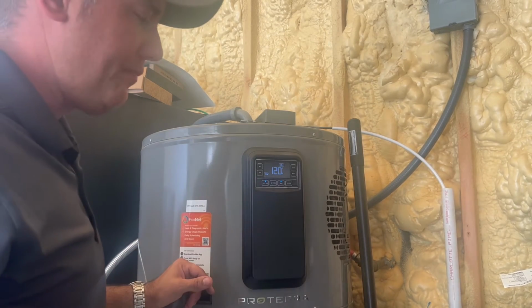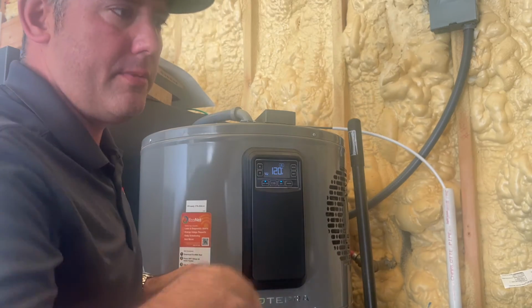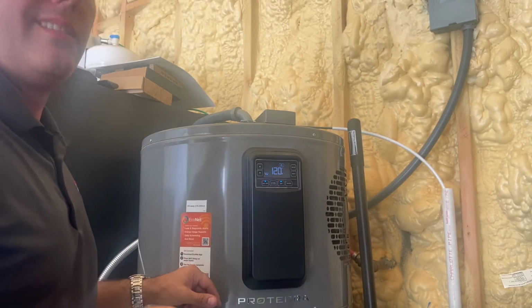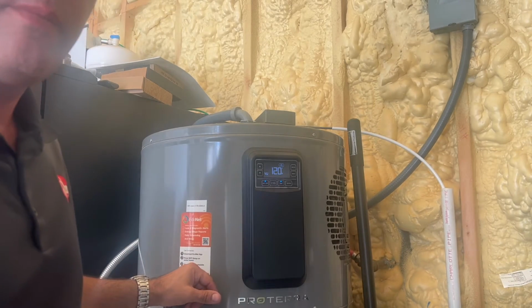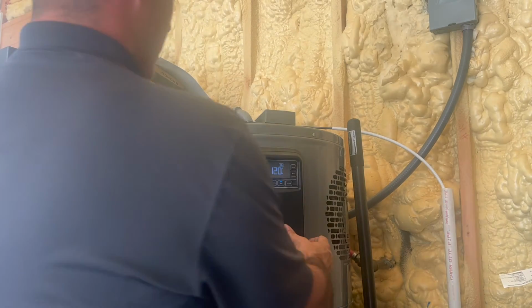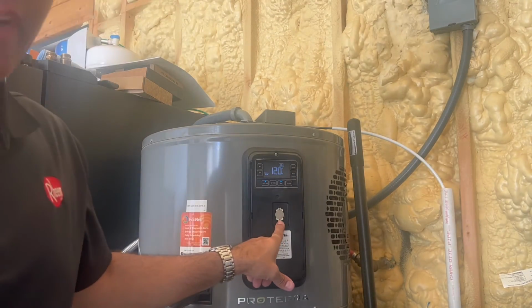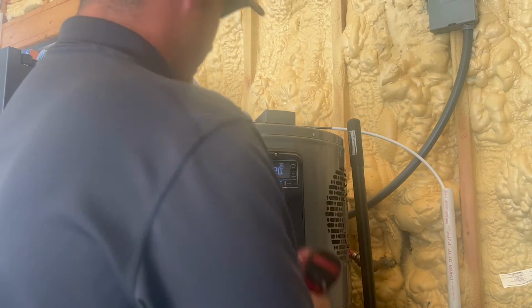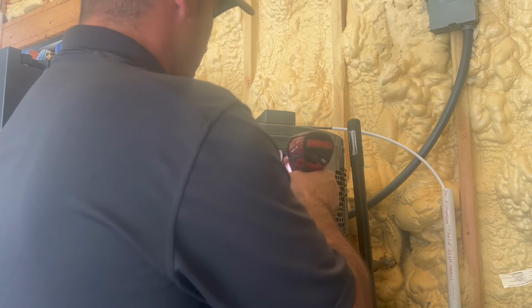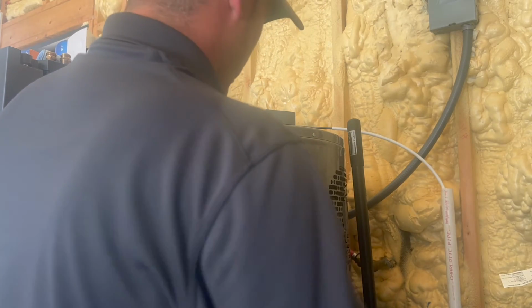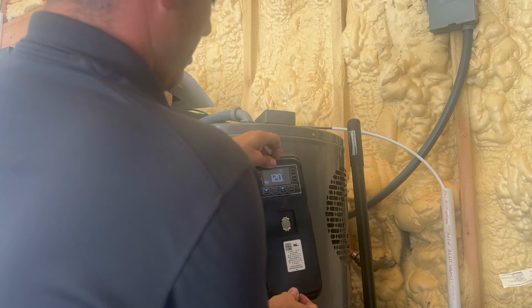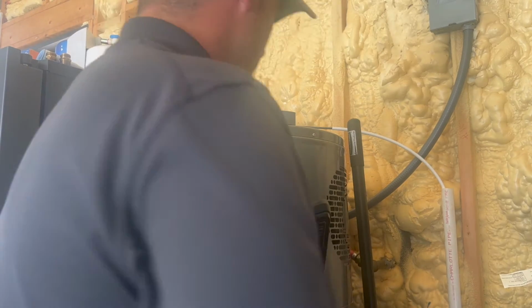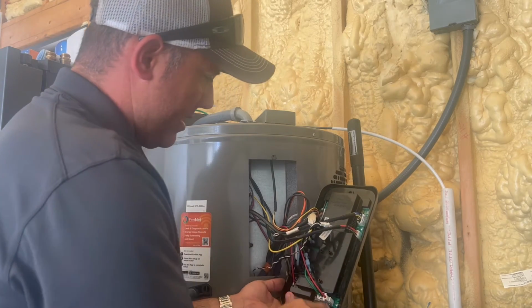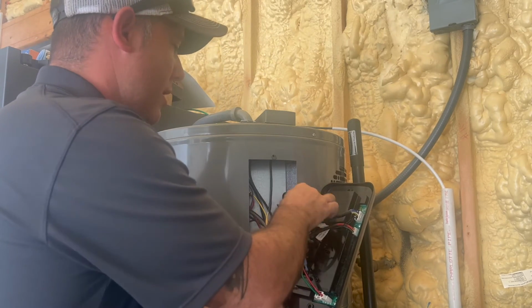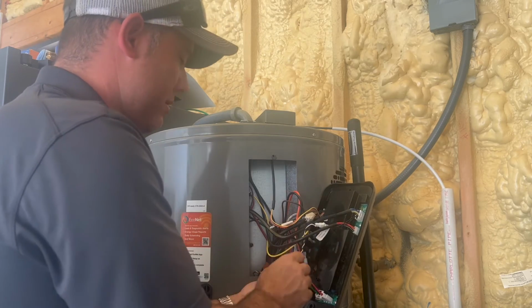Now, moving on from that, if we've done all of these tests and we suspect that there's just a problem with the heater, let's look at the data we can get from this unit and figure out what's going on. We're going to start at the top. Panel comes off, battery right here, memory backup. 2 screws. Two screws hold this user interface on. In the back is the main power that comes in along with your wiring harnesses. These wiring harnesses connect everything inside of the heater from the lower elements to all the sensors, your thermistors.